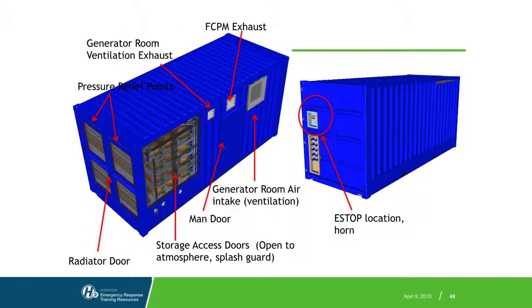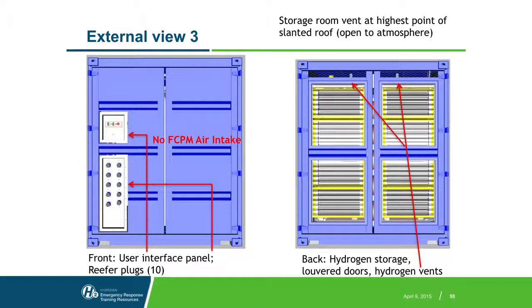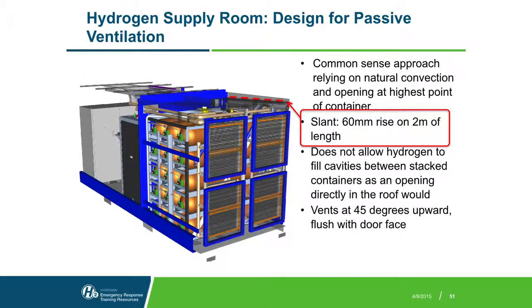All right, some more diagrams for you. We talked about the air intake, exhaust, the vent relief ports here on this end, and they will be orienting the unit such that those are facing out. You'll notice on the hydrogen end, this is all open, and there's a splash guard. Another view of the front and back, if you will: user interface, plugs, and the vents with the louvered doors. Again, illustrating the rise in the roof there, a common sense approach for natural ventilation should you have a leak in that storage area.